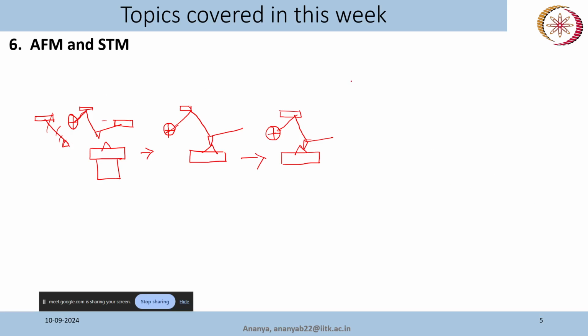Mechanism wise, STM is a bit different. It is based on tunneling current. So again, suppose this is your sample, it has some surface profile like this. Now there will be again a piezoelectric material, and there will be your conducting tip.